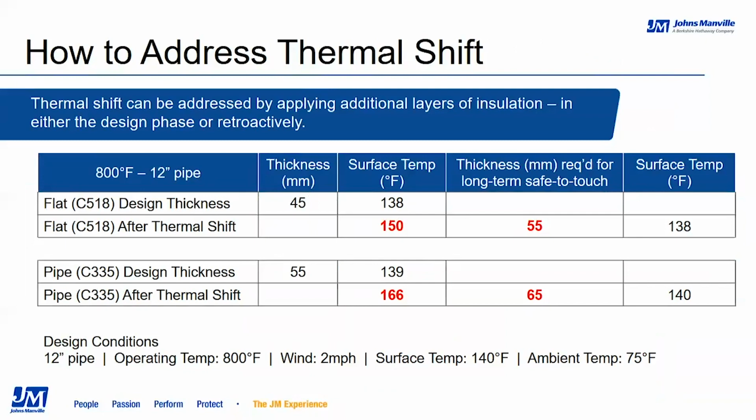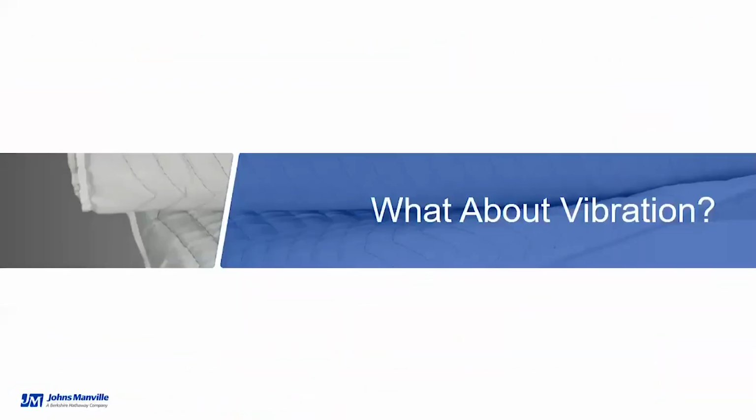So my message to engineers, specifiers, and owners is always ensure you're using the correct data when specifying thin blanket insulations, and always remember thermal shift if you're considering using aerogel technologies. Now I'm going to pass it back to Kim. Great, thank you so much, Jeff.